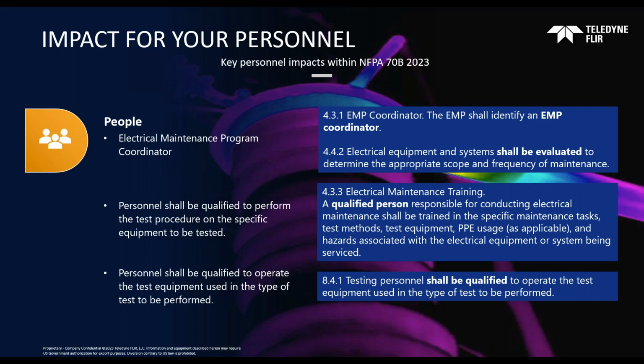On the personnel side, understanding that they need to be qualified to perform the test procedures themselves. Any person responsible for conducting electrical maintenance is going to be trained in specific tasks, testing methods, test equipment, and PPE usage as applicable, along with hazards associated with the electrical equipment or system being serviced. This is where the tie-in to NFPA-70E comes in with 70B. We need all that information documented to determine our staff are properly trained to perform those activities.